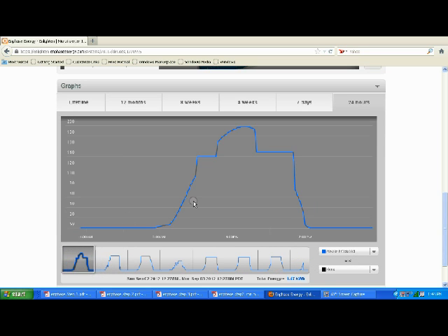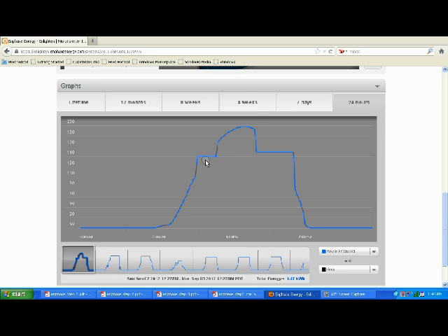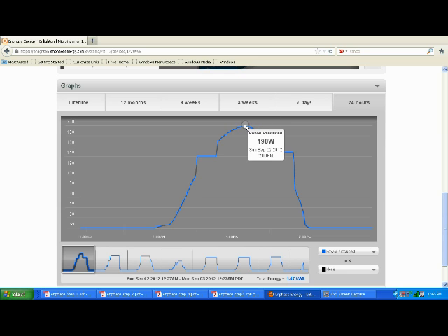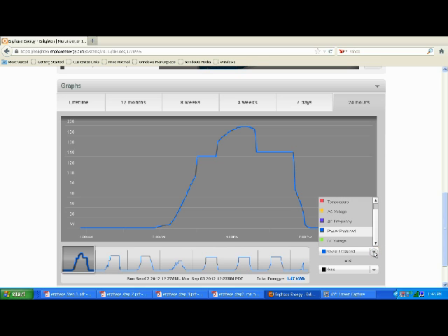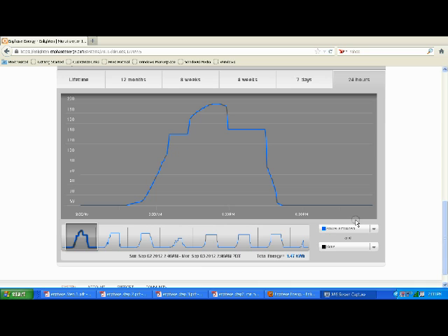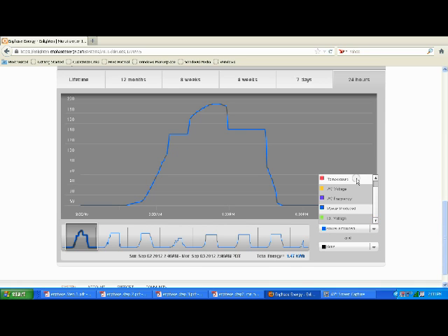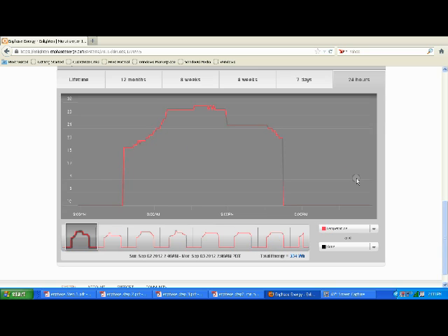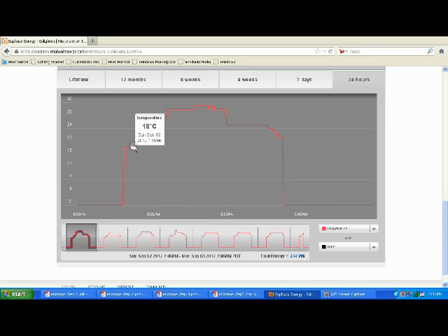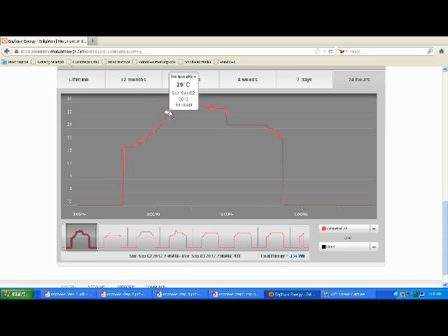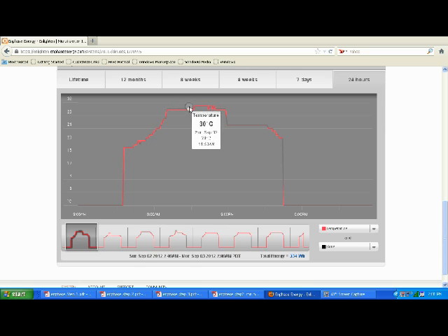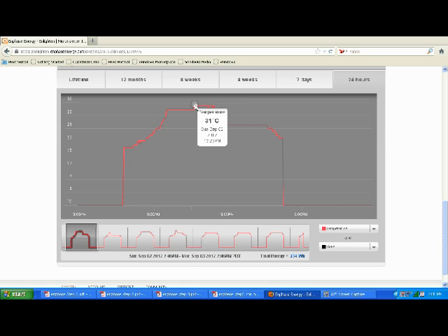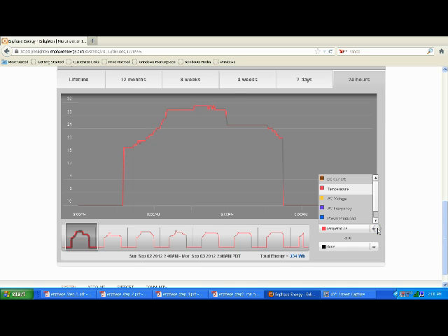This is the power this panel's produced over the last seven days. I can see the time and the watts it's produced - this panel hit 198 watts at two o'clock. Let's say I want to look at the panel's temperature on this particular day. I can click on this and see the temperature at any given point. The panel temperature topped off at about 31 degrees. As you know, there's a relationship between panel temperature and production. In general, the cooler the panels, the greater the production. The hotter the panels, the less production.